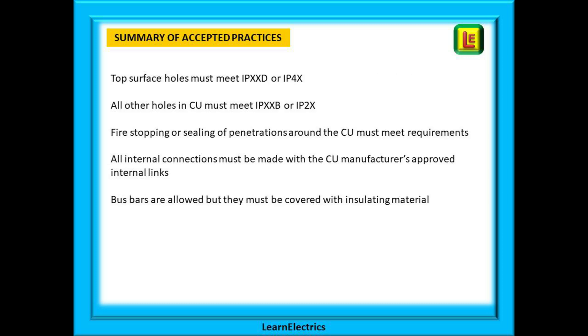Top surface holes in consumer units or cabinets must meet IPXXD or IP4X — in other words, maximum one millimetre holes. All other holes in consumer units must meet IPXXB or IP2X, which is a 12.5 millimetre gap. Fire stopping or sealing of penetrations around the consumer unit must meet building regulations requirements. All internal connections must be made with the consumer unit manufacturer's approved internal links; bus bars are also allowed but must be covered with insulating material. Ideally the consumer unit should be installed as close as possible to the service head to reduce cable length and the potential for mechanical damage.